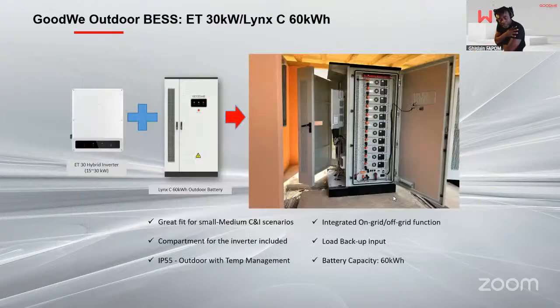Now, the same platform from 15 to 30 kilowatt can also join a system we call a BESS, the actual first BESS system that we offer: a small C&I, IP55 outdoor cabinet with temperature management. Once you build the cabinet with one ET30, the battery and the battery cabinet, you have a self-sustained system that can monitor itself. The temperature control makes sure that the system doesn't overheat in summer, because the air conditioning unit will be monitoring at module and cell level to make sure the temperatures are within the windows of operability.